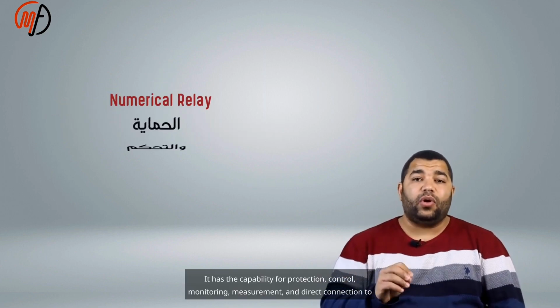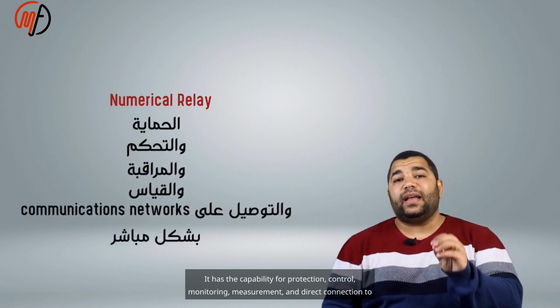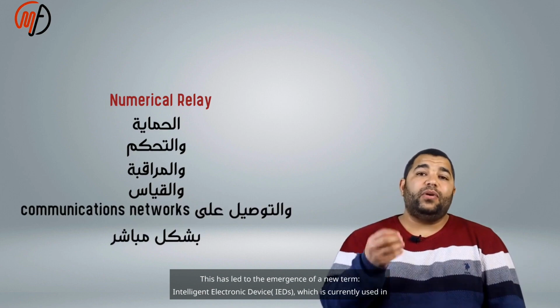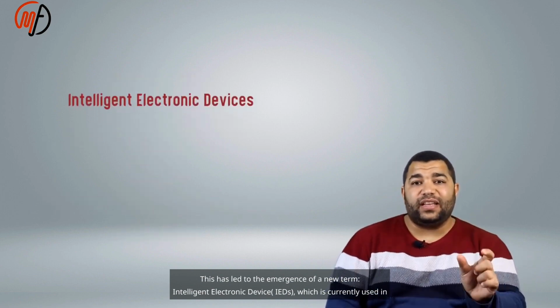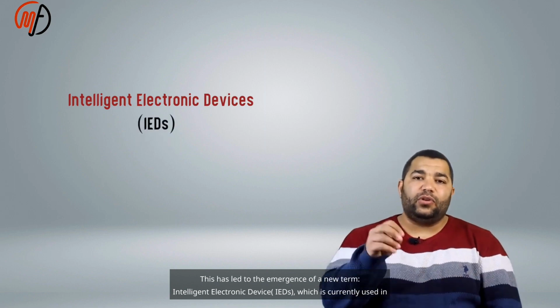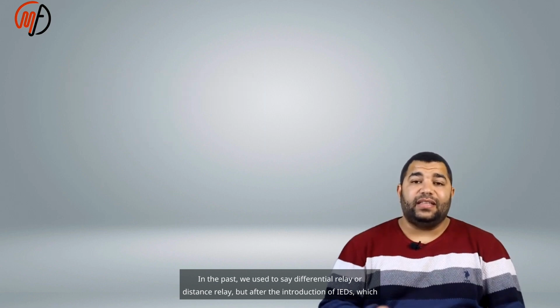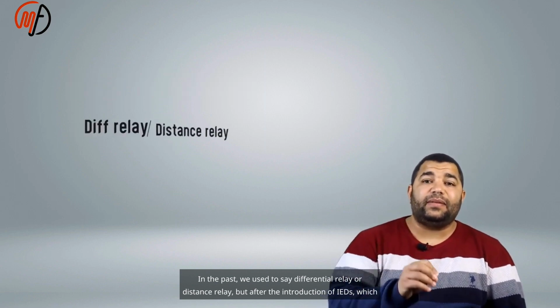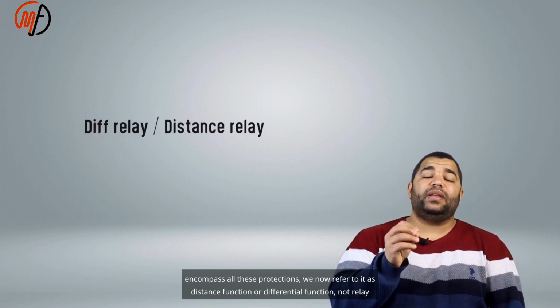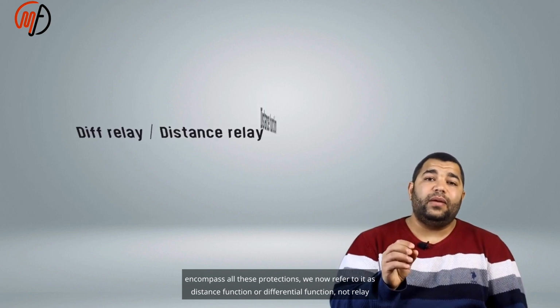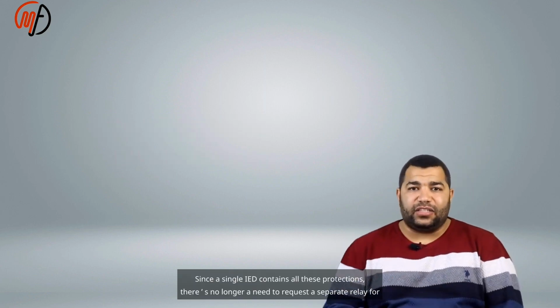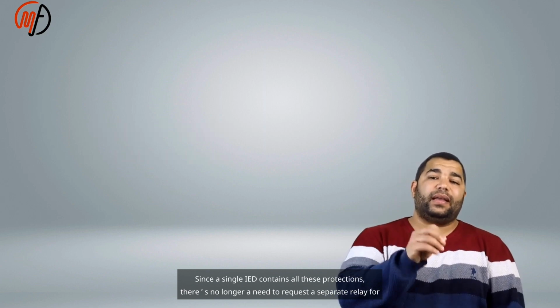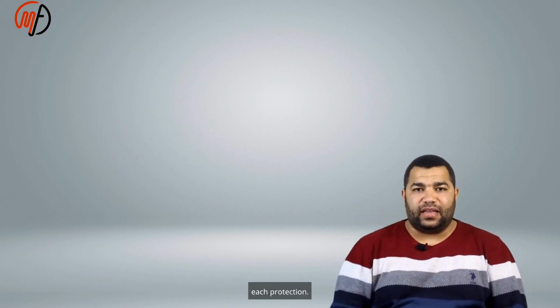And with development, it has the capability for protection, control, monitoring, measurement, and direct connection to communication networks. This has led to the emergence of a new term, Intelligent Electronic Device, IEDs, which is currently used in substations. In the past, we used to say differential relay or distance relay, but after the introduction of IEDs, which encompass all these protections, we now refer to it as distance function or differential function, not relay. Since a single IED contains all these protections, there's no longer a need to request a separate relay for each protection. This way, I have significantly reduced the number of relays.